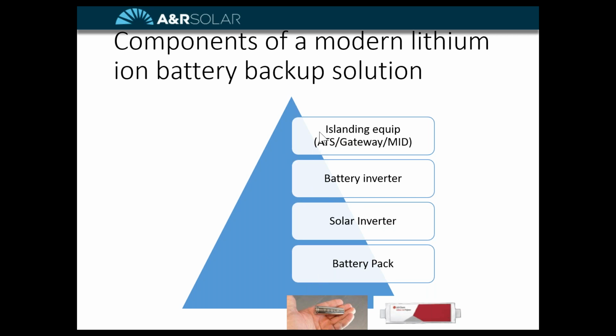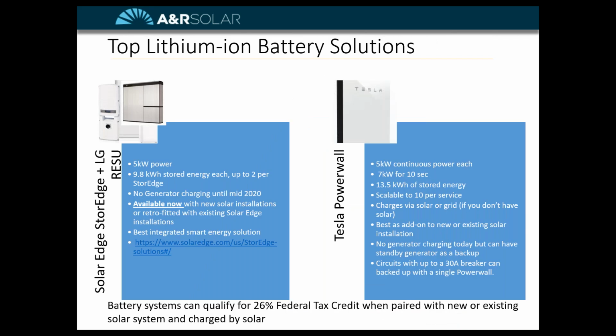Finally, mandated by code, by the National Electric Code, we have to have islanding equipment. You'll hear it called an automatic transfer switch or ATS, a gateway, an MID, a microgrid interconnection device—lots of different names for it. But this island equipment is specific to the manufacturer, not just a generic transfer switch.